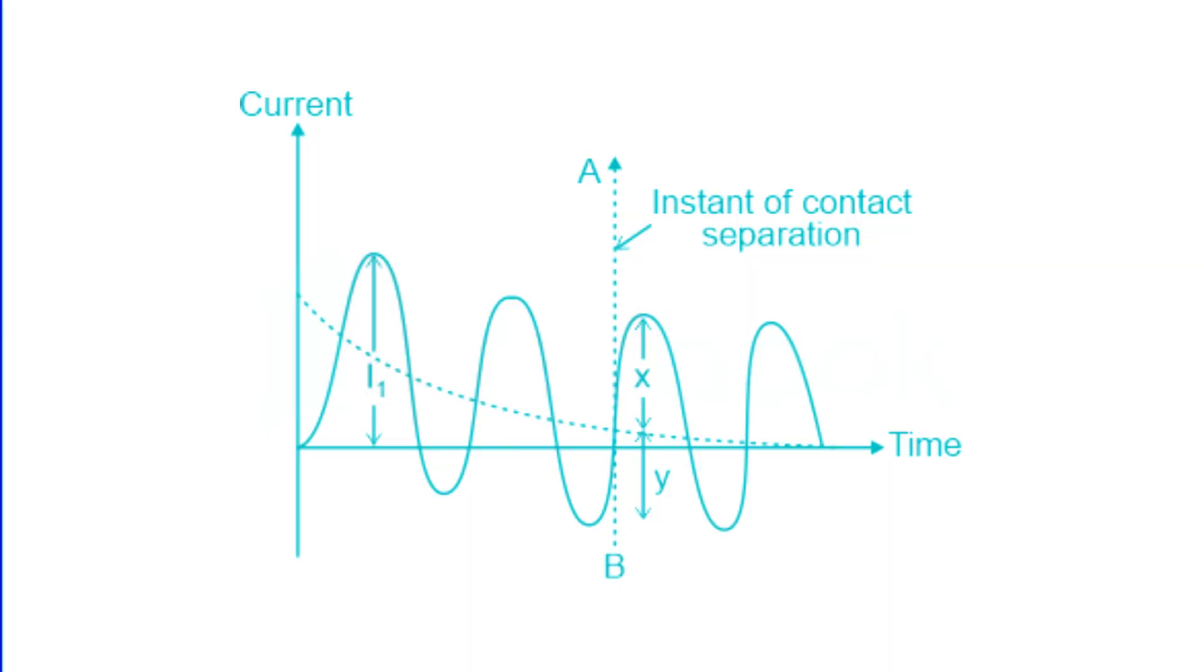The making current of a circuit breaker is the peak value of the maximum current loop during the sub-transient condition, including the DC component when the breaker closes. I one represents the making current of the circuit breaker including the DC component.